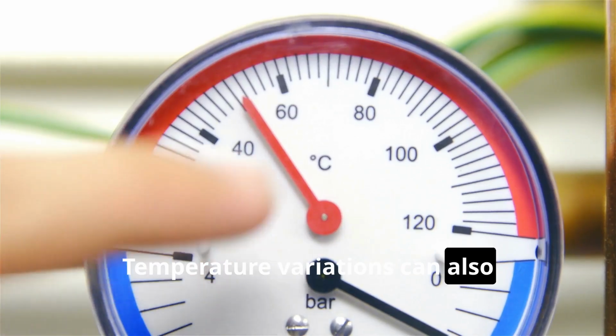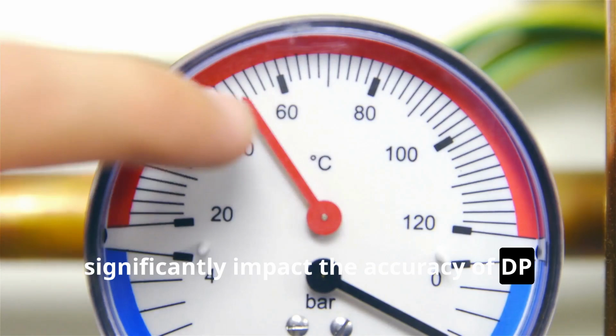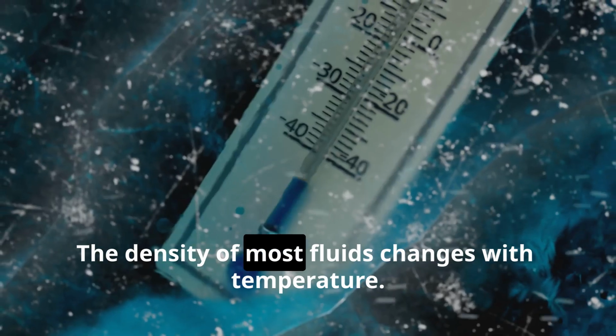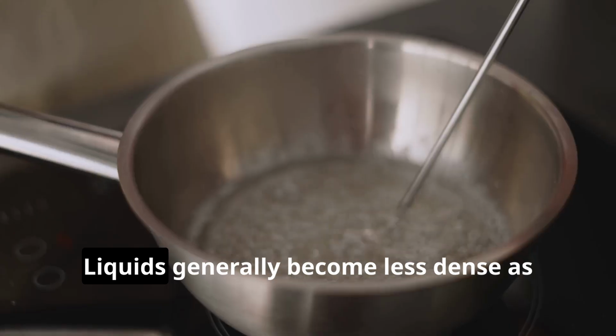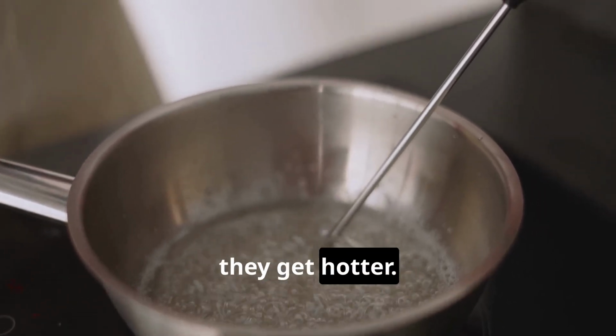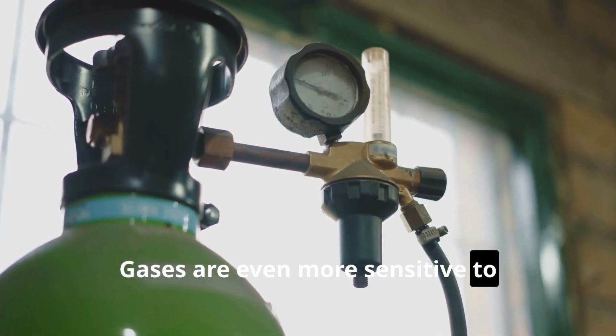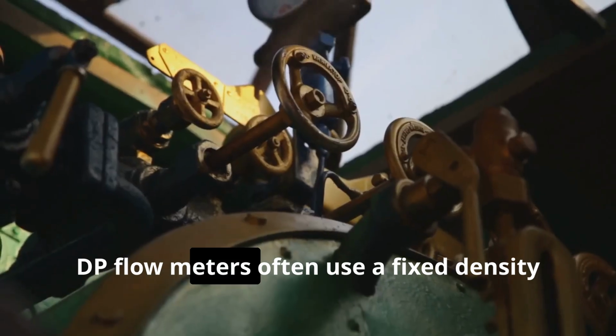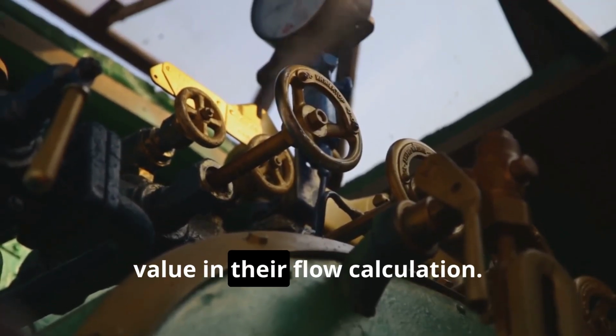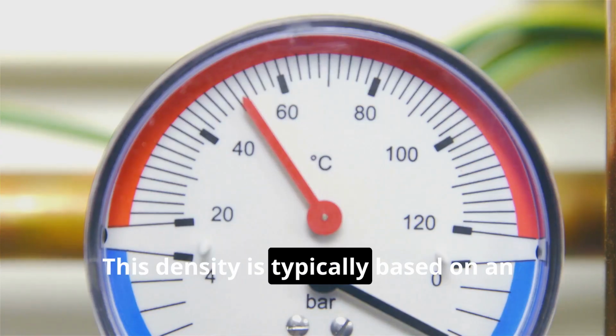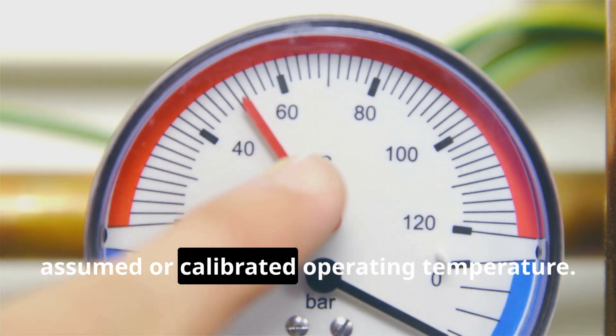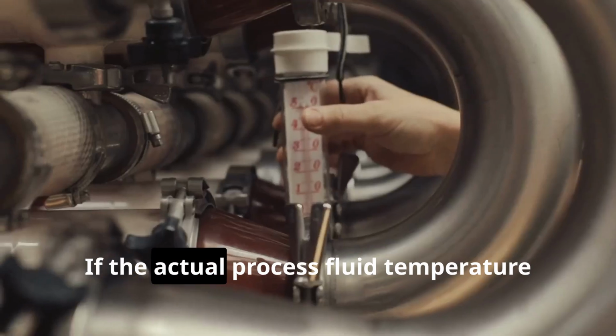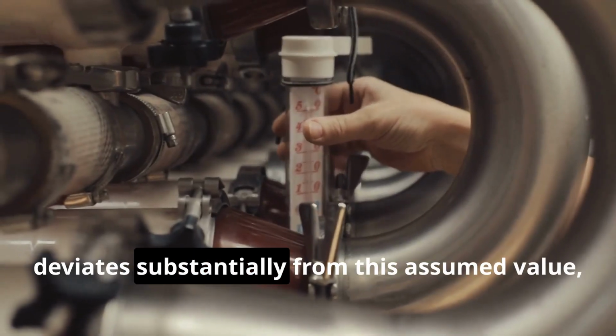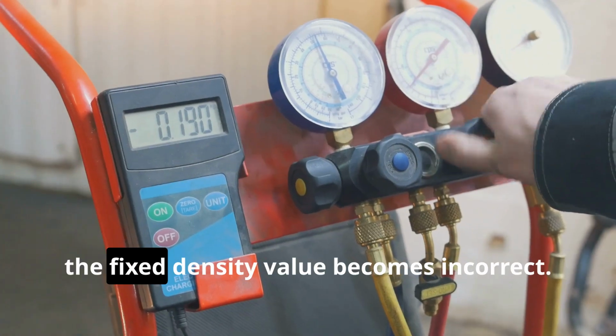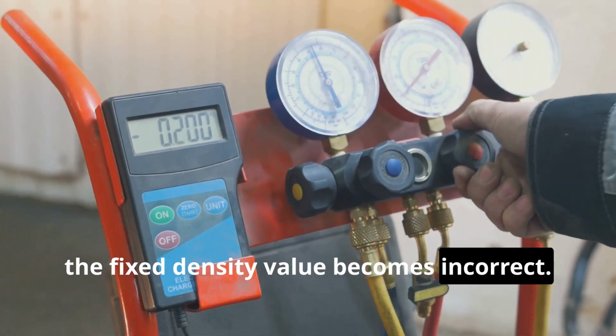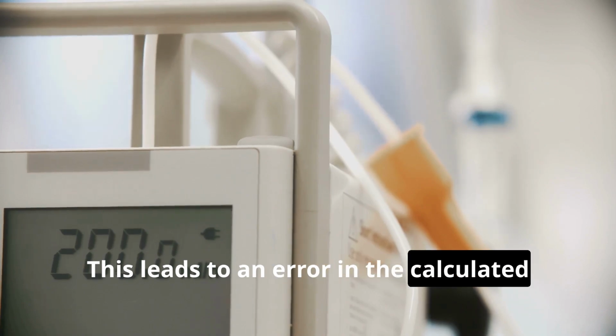Temperature variations can also significantly impact the accuracy of DP flow meter readings. The density of most fluids changes with temperature. Liquids generally become less dense as they get hotter. Gases are even more sensitive to temperature changes. DP flow meters often use a fixed density value in their flow calculation. This density is typically based on an assumed or calibrated operating temperature. If the actual process fluid temperature deviates substantially from this assumed value, the fixed density value becomes incorrect. This leads to an error in the calculated flow rate.